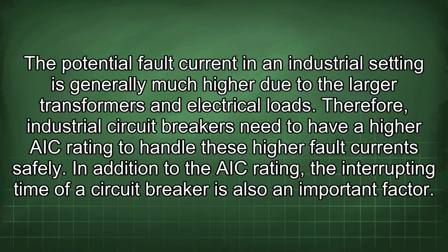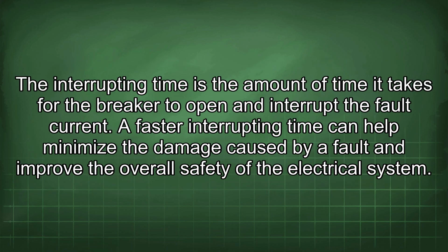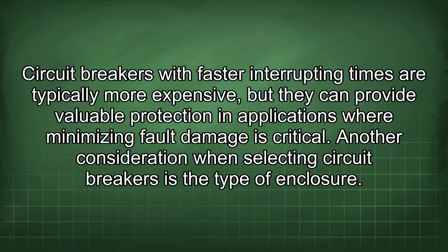In addition to the AIC rating, the interrupting time of a circuit breaker is also an important factor. The interrupting time is the amount of time it takes for the breaker to open and interrupt the fault current. A faster interrupting time can help minimize the damage caused by a fault and improve the overall safety of the electrical system. Circuit breakers with faster interrupting times are typically more expensive, but they can provide valuable protection in applications where minimizing fault damage is critical.